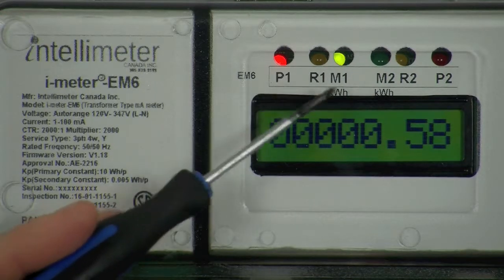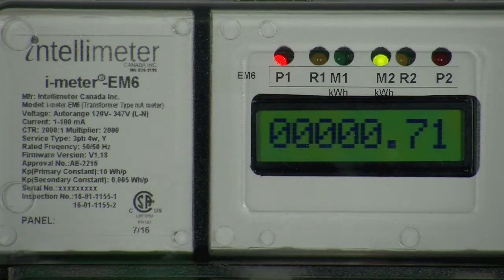The blinking amber LEDs can also be a result of the CT leads being reversed at the terminals inside the meter. Make sure that the black CT lead wire is in the negative terminal and that the white CT lead wire is in the positive terminal. We're going to repeat these checks for CT2 and CT3. If everything just mentioned checks out, then there is most likely a problem with the reference voltage.